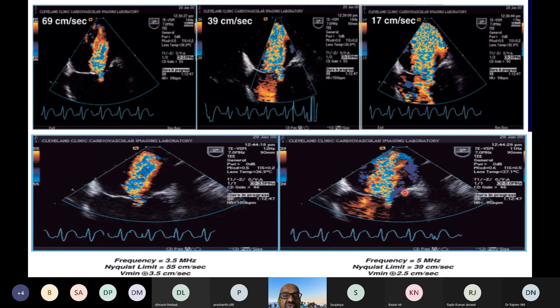And here some of the major differences between color flow Doppler, pulse wave Doppler, and continuous wave Doppler are shown. Quickly revising, this is a revision of what we said in the last 20-30 minutes. In continuous wave Doppler, there is actually no sample volume. We do not place a sample volume. The velocity is measured all across the echo beam, whereas in pulse wave Doppler, we place a sample volume which is 2 to 5 millimeters in thickness. We actually tell the machine where we want to measure the velocity.